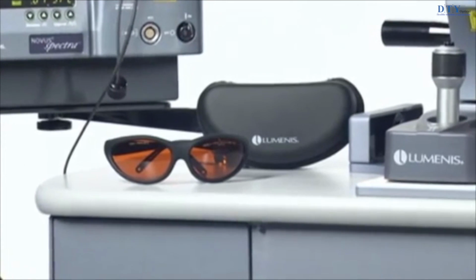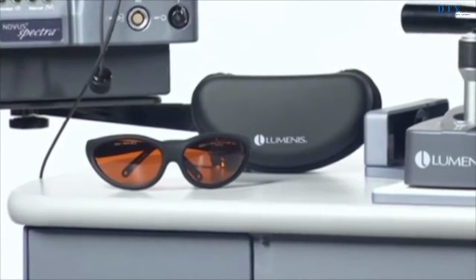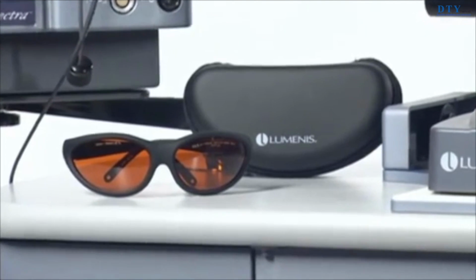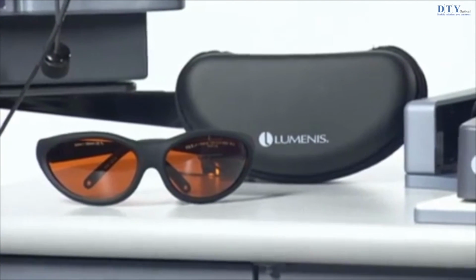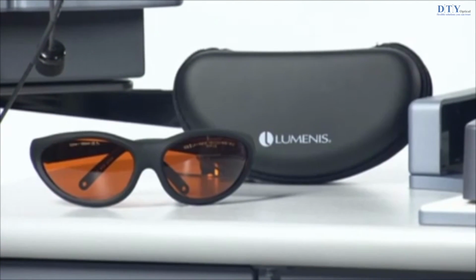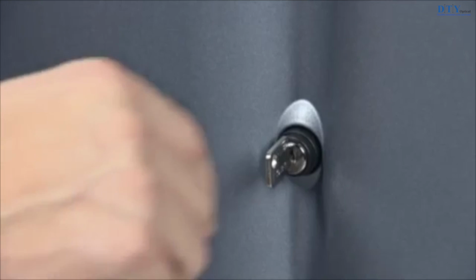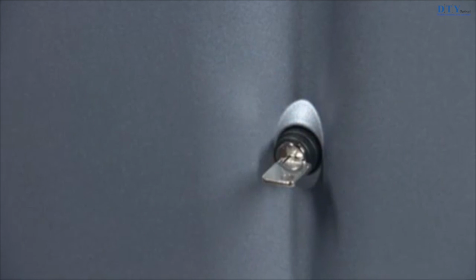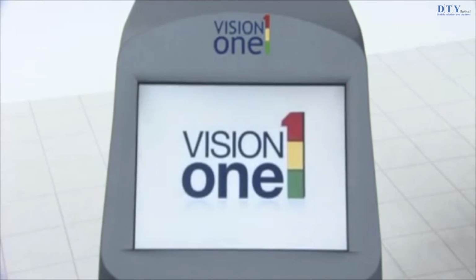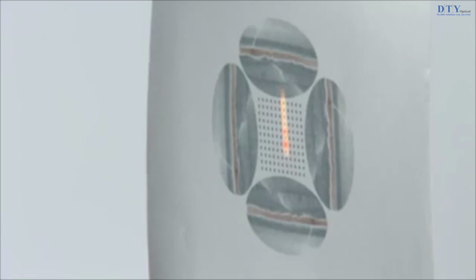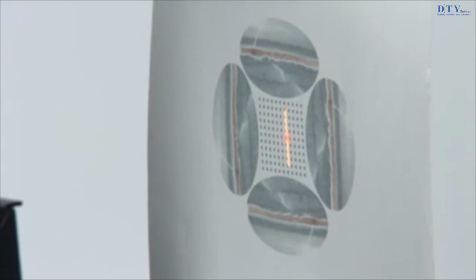Make sure that all persons in the treatment room are wearing the appropriate laser safety eyewear. See Laser Safety Eyewear in the Safety Regulatory chapter for detailed laser safety eyewear information. Then turn on the laser as instructed in the Laser Console Basics in this presentation, and verify the aiming beam as instructed in the appropriate delivery device operator manuals.